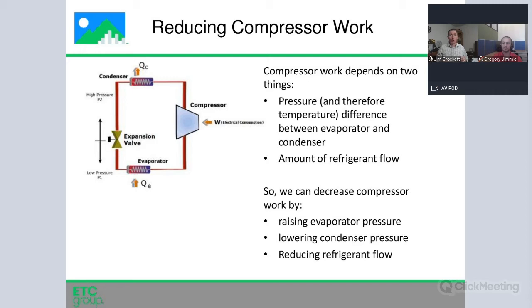So the pressure required to go from low pressure to high pressure, you'll hear the term lift used in the industry. And lift is basically the distance between the low pressure and the high pressure sides of the system. So one way is to decrease lift, and we can do that either by raising the low side or decreasing the high side. And I'll talk briefly about both of those.